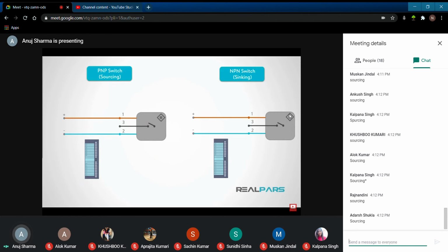In order to connect a 3-wire discrete DC device to the PLC, we will need to identify whether the device is an NPN or a PNP type. NPN and PNP are 2 types of bipolar transistors, which are simply solid-state switches. You should always check the manufacturer's data sheet for the device you are going to connect to the PLC to make sure you know its configuration. For now, just remember the NPN switches are referred to as sinking, and PNP switches are referred to as sourcing.